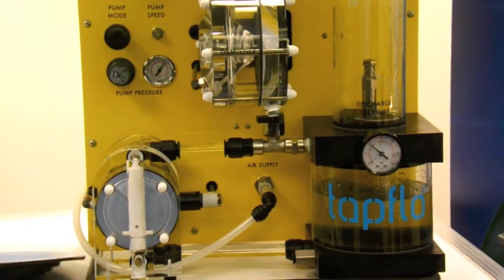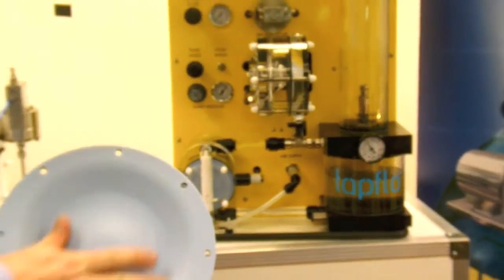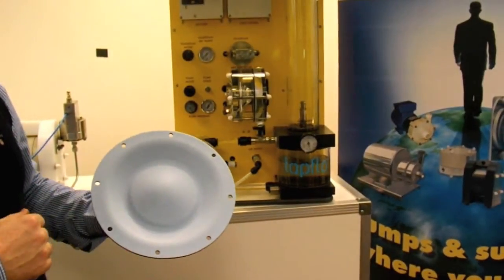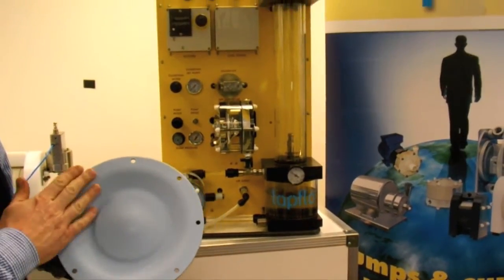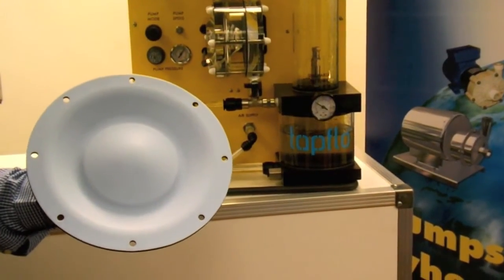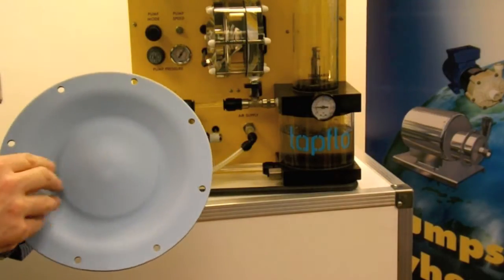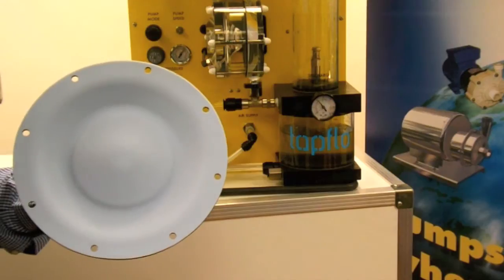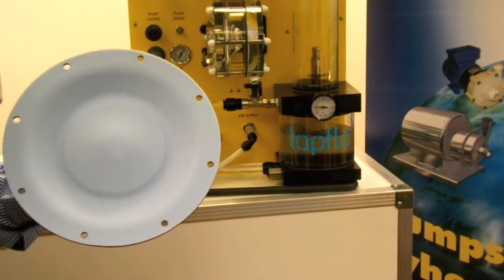One thing worth pointing out is that all TAPFLO diaphragms are one piece composite diaphragms. In this case it has a PTFE face on it but it gives you a nice smooth finish which makes it very easy to clean and to keep the pump clean during operations. Also because there are no joints or caps on the front of it, there is no potential for a leak back through to the air side of the pump.